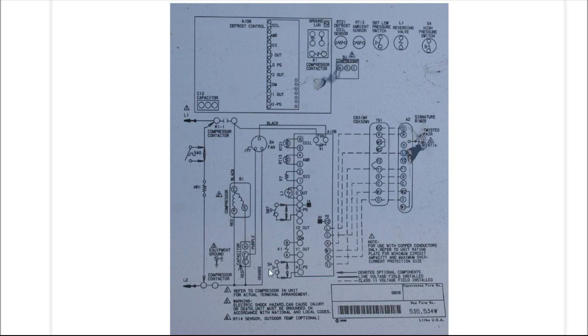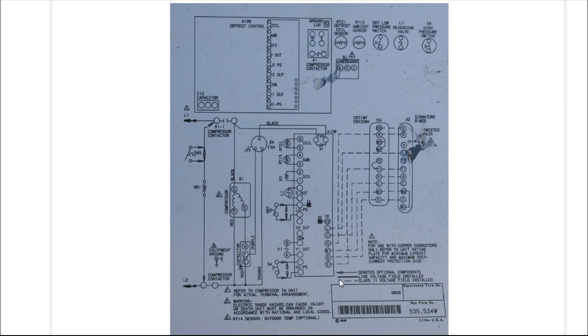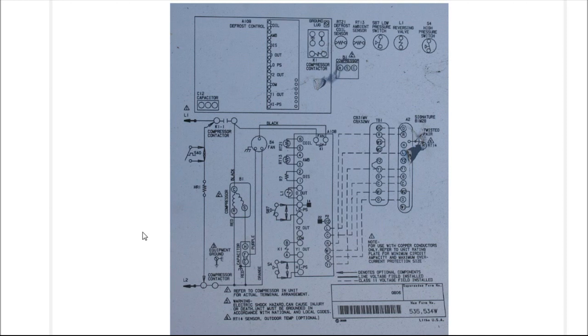Just this arrow denotes optional components. Mine happens to have the high-pressure and low-pressure switch; the one you're working on may not. The next thing, line voltage field installed, this is going to hold true on all of the ladder diagrams, doesn't matter which manufacturer that you're looking at or what type of equipment. But that is the line voltage, the high voltage coming from the home, usually designated by L1 and L2.